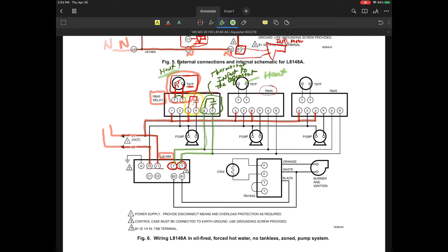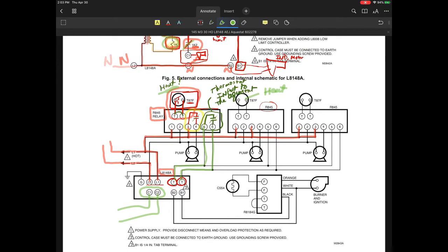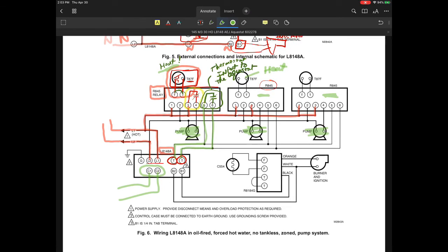Now, let's say we have another one of these that maybe has a demand. So let's say this one now calls for heat. So at this point, when the first one was running, the circulator was energized. But remember, oftentimes on these, we don't even power anything on C1 and C2, because in a zoning pump application, this is going to control your pump, and this one is going to control this pump, and this relay is going to control this pump. So the burner or the Aquastat circuit isn't really doing anything other than it's just there. It's available if you wanted to use it, but it's not doing anything.